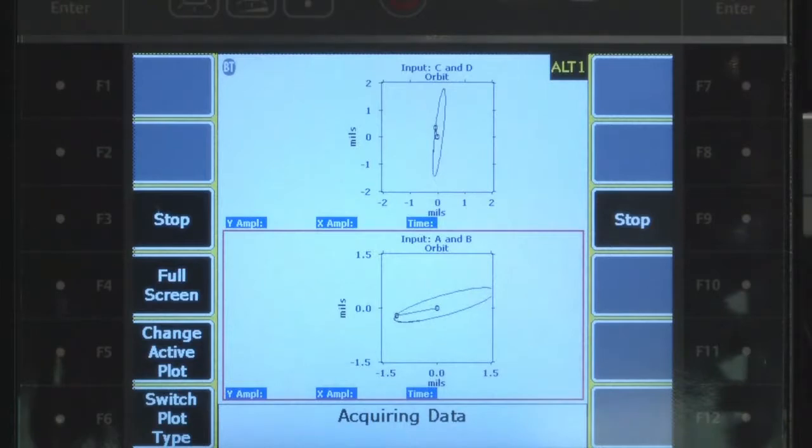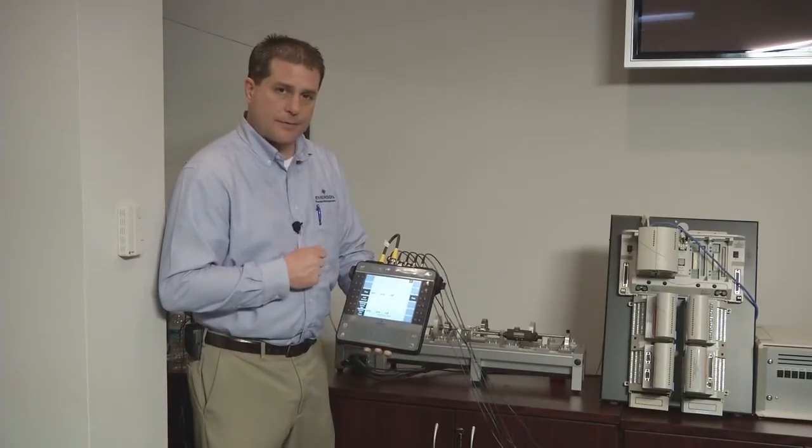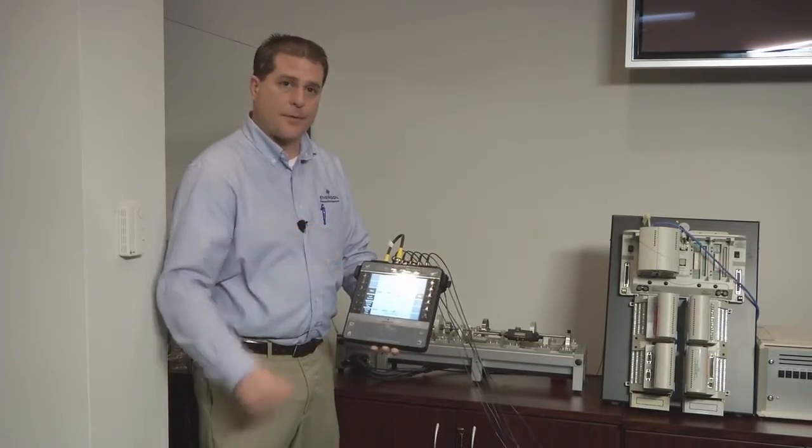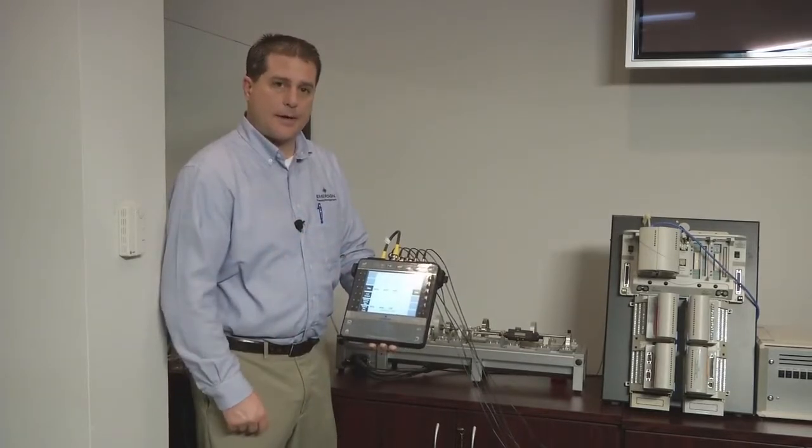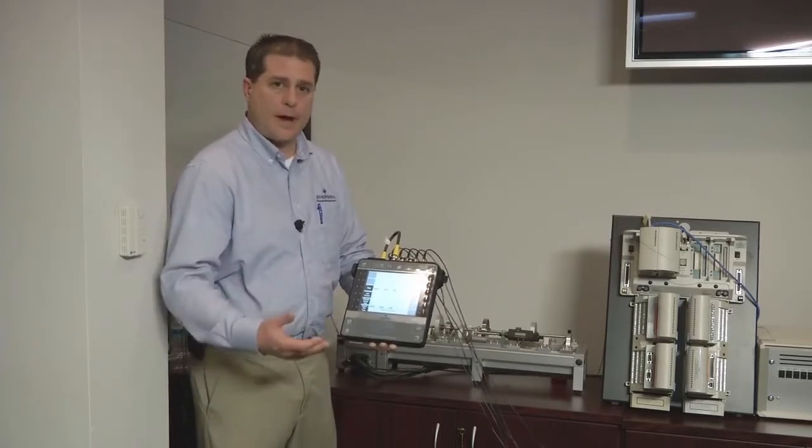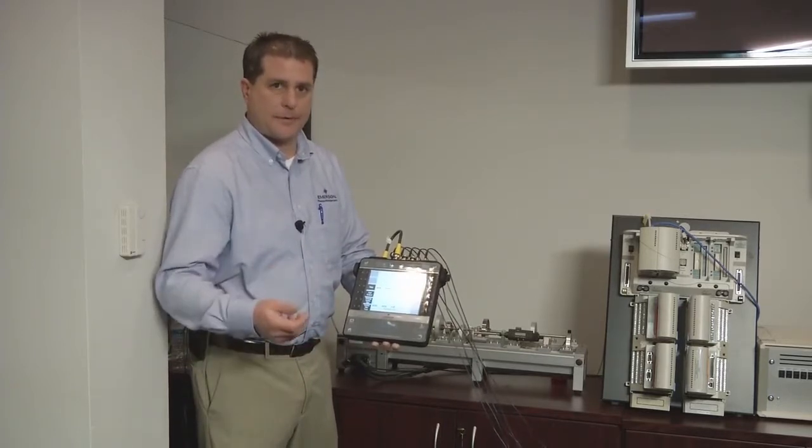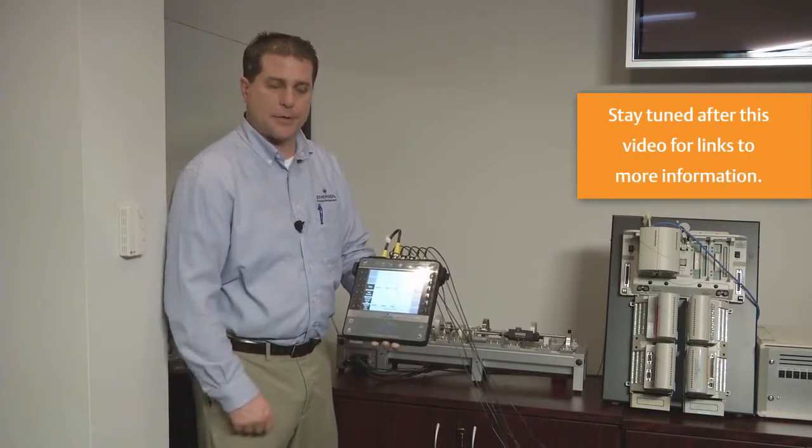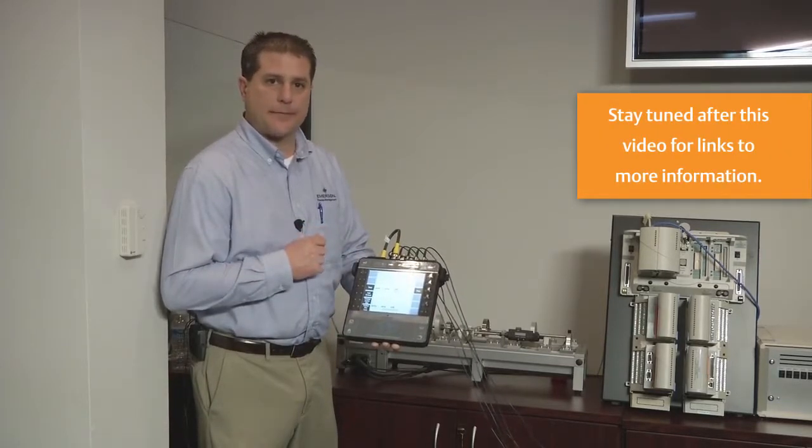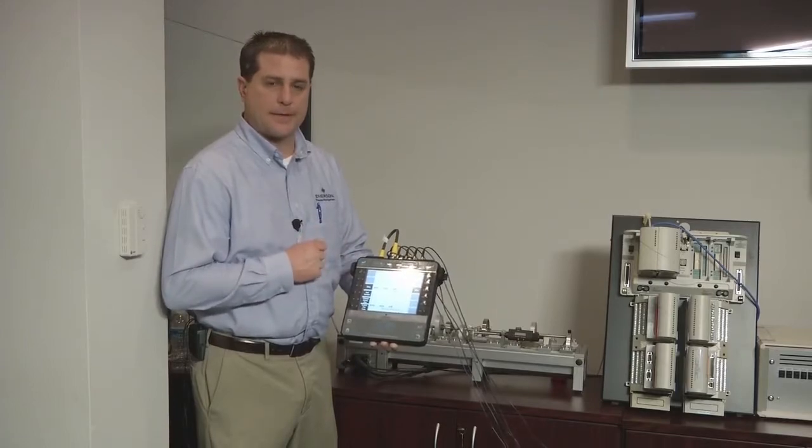So you would be able to see any changes in the rotor condition if you had a shaft rub or ran through a resonance. This is very beneficial diagnostically where we can monitor a start up or a shut down of this sleeve bearing turbo machine or on a route basis. You could go out there on your route and connect up to this protection panel to take readings for predicting the health of this sleeve bearing machine.